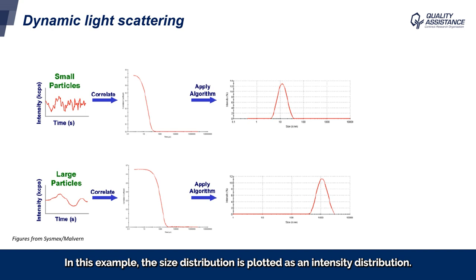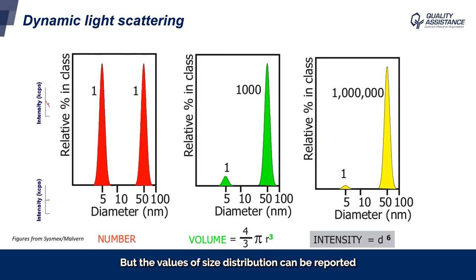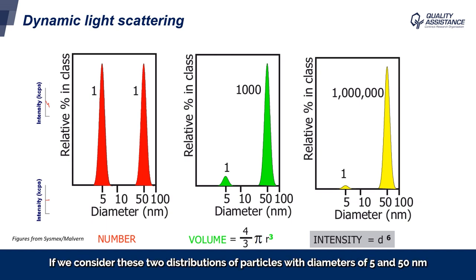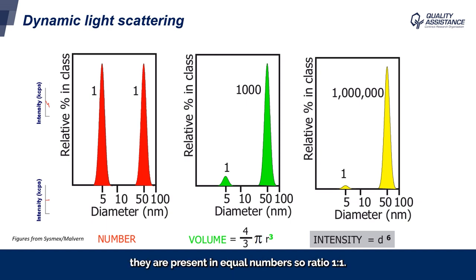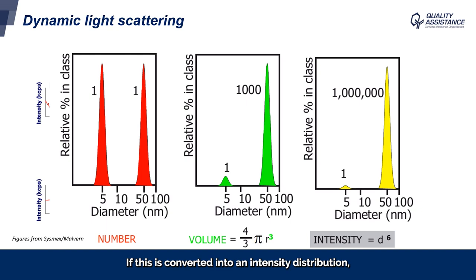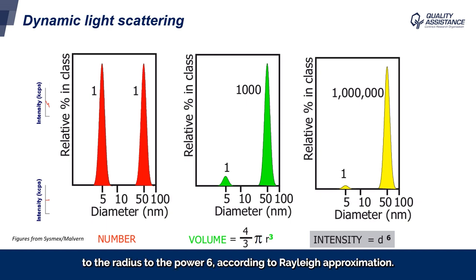In this example, the size distribution is plotted as an intensity distribution. But the values of size distribution can be reported by number, intensity, or volume, as we can see on these plots. If we consider two distributions of particles with diameters of 5 and 50 nanometers present in equal numbers — ratio 1 to 1 — if this is converted into volume, the ratio of the peaks would change to 1 to 1000, related to the calculation of the volume of a sphere. If converted into an intensity distribution, the ratio is now 1 to 1 million, because intensity is proportional to the radius to the power 6, according to the Rayleigh approximation.